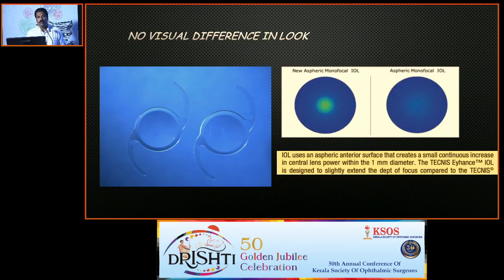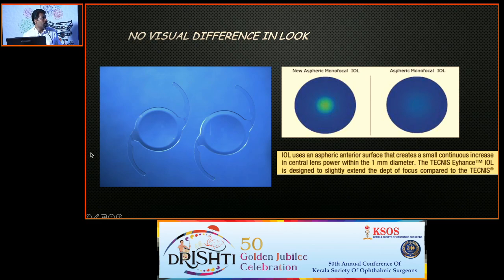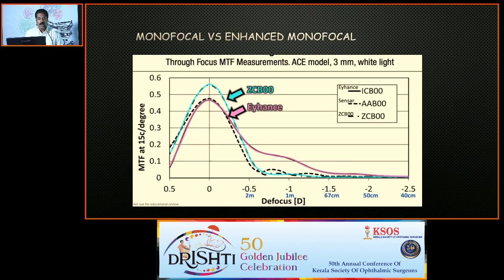About enhanced monofocal — if you visually see, there is no difference between the two lenses. One is an enhanced monofocal and the other is just a monofocal. They look very similar. How the enhanced monofocal works is: it is essentially a monofocal lens, except the central 1mm — the anterior asphericity of the central 1mm — is made with higher order optics. There is a gradual increment of power given only in that center. That one mm area can give up to +0.5 to +0.75 extra power. That is what is called an enhanced monofocal.